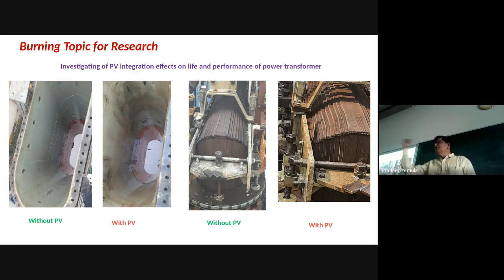We always used to say this is primary, supply comes in, secondary, supply is delivered. Now because of distributed generation or renewables, we do not know which is primary anymore. Primary means where we are giving supply, but it is not known. With this doubt, we opened this transformer recently, even though our schedule is to open transformers only after 15 years. But after just 8 years, we opened it to see what is going on. So now we are repairing it, otherwise it will fail.